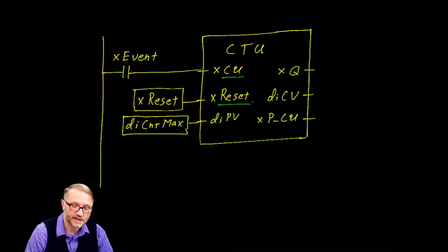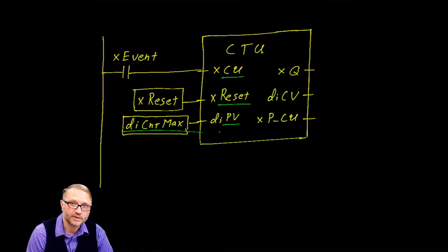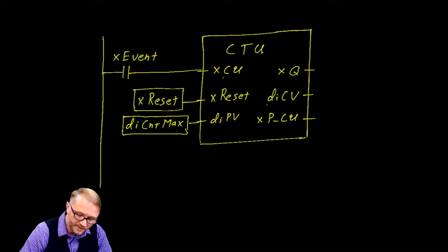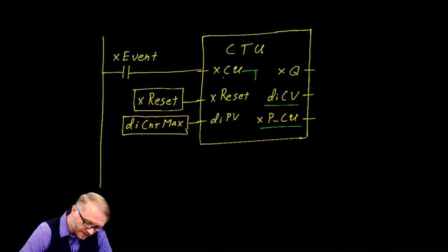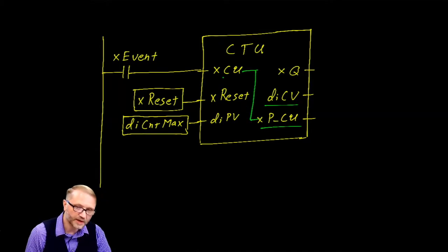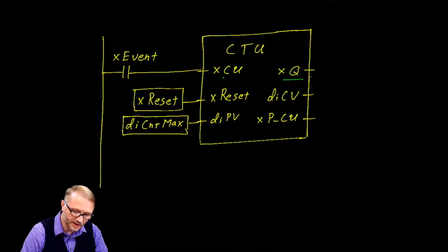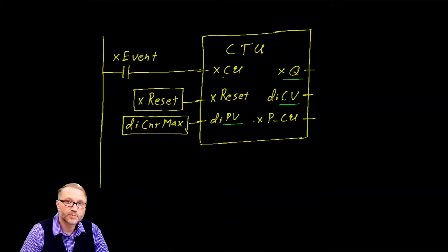Reset resets our count back to zero. This is the program value — I like to think of that as the maximum count that this counter will achieve. We have the current value of the count. And this one's rather interesting: this is the previous value of count up. So internally, you could think of these two as simply being wired together — whatever count up does, the previous value of count up will do the same. And finally, we have a Q output, and the Q output will be high when the current value has achieved the program value.